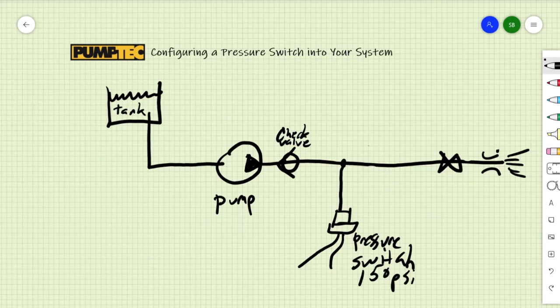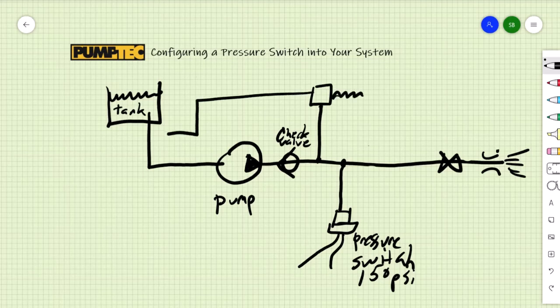Another thing to consider when using a pressure switch is the use of an overpressure safety device. Here I'm showing a regulator with a discharge back to tank. Since this safety device won't be used typically unless there's some other failure, you can actually run the discharge just out to atmosphere.